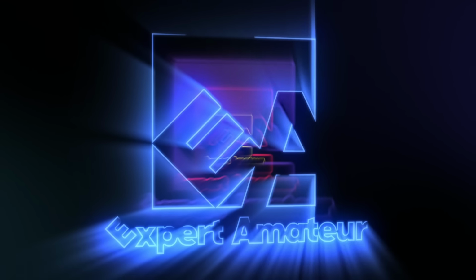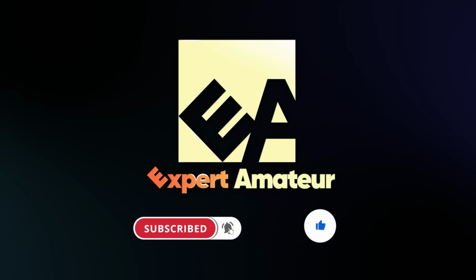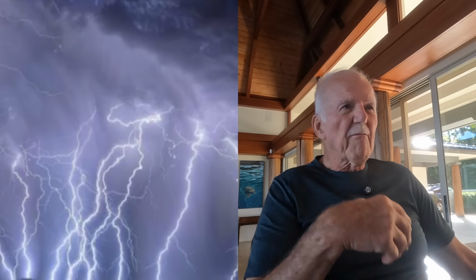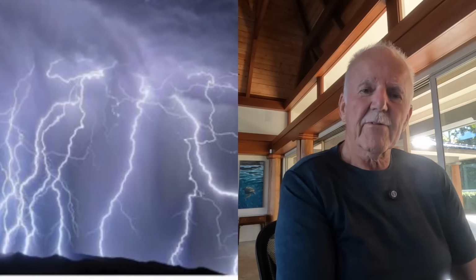So our topic today is solar bonding and grounding, which is very boring unless you get whacked by a lightning bolt. Solar installations are sort of a lightning magnet. The metal frames on your roof or in an open area, metal racking, a bunch of wires leading directly into the guts of your equipment. If there's a nearby lightning strike, it'll induce high voltages into your installation, and that can wind up in your equipment. If it does, it's slagged, most likely. So it can be very expensive to not pay attention to this.